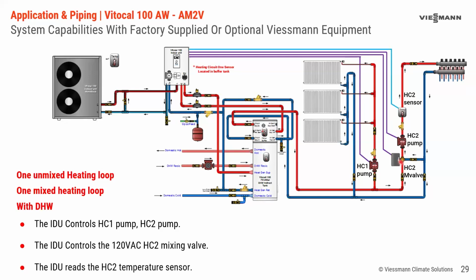And then the temperature sensor for circuit 2. Remember, the temperature sensor for circuit 1 is in the buffer tank. Temperature sensor for circuit 2 is in the pipe downstream of the mixing valve, so the mixing valve can control it.